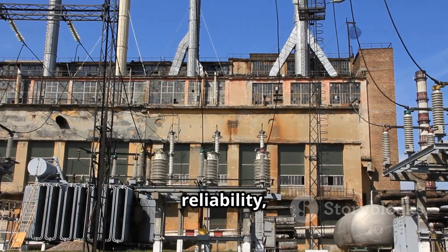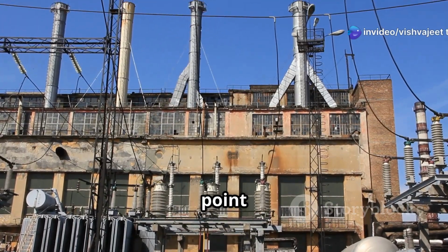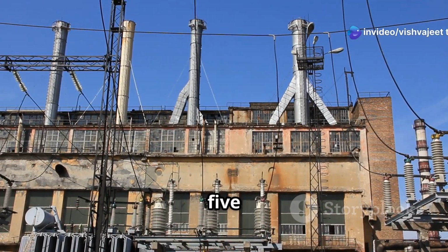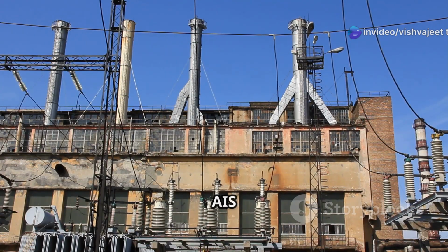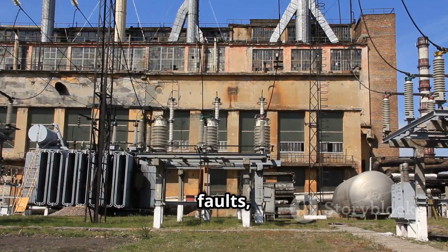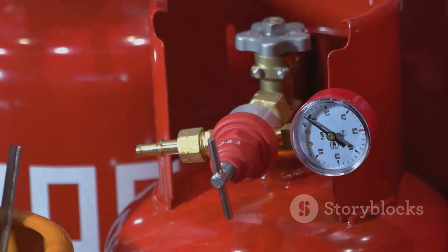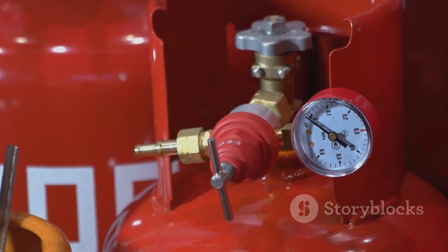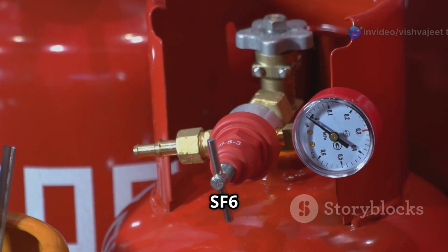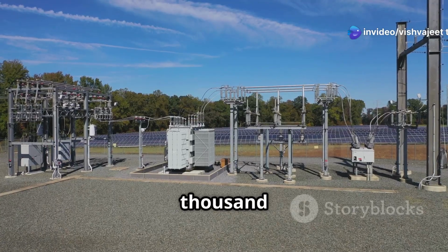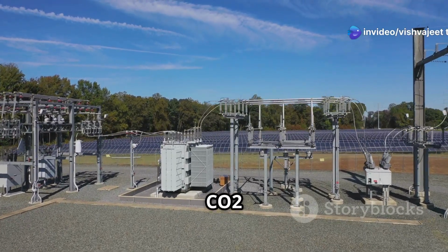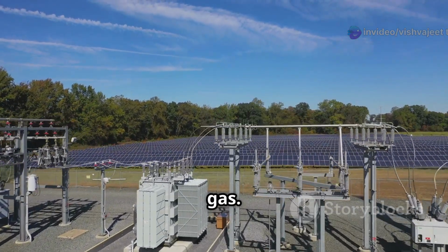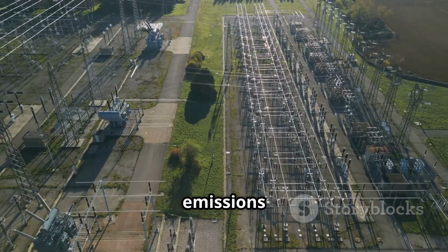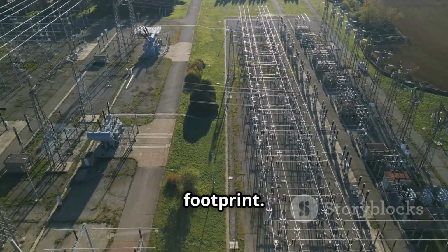GIS has higher reliability, typically 99.9% versus 99.5% for AIS. AIS is more prone to external faults, animals, pollution, and weather. GIS uses SF6 gas, which is 23,500 times more potent than CO2 as a greenhouse gas. AIS has no F-gas emissions, but has a larger physical footprint.